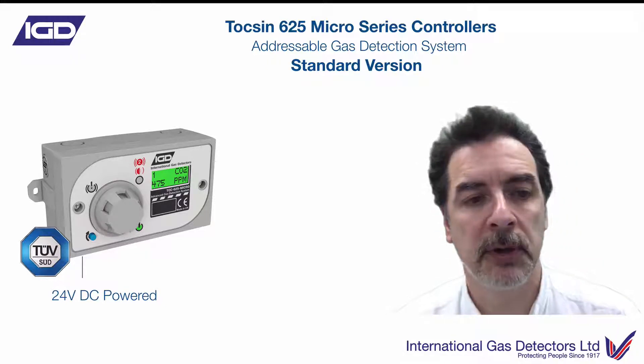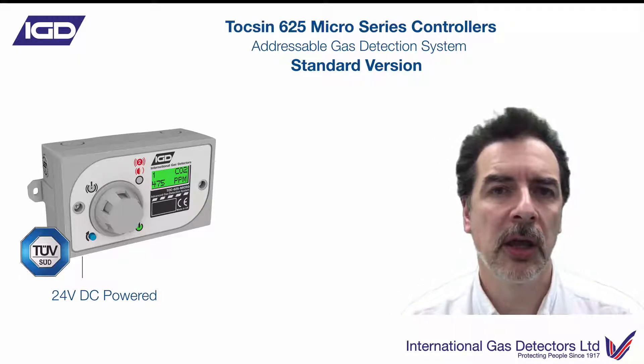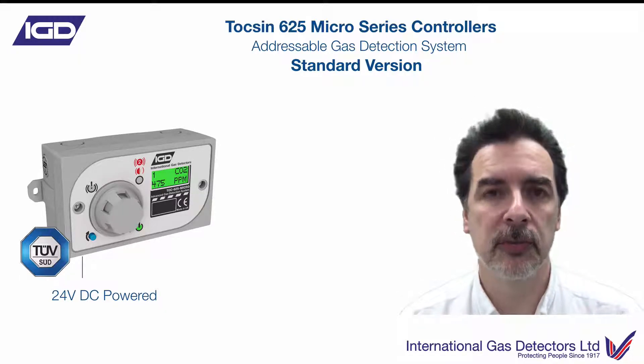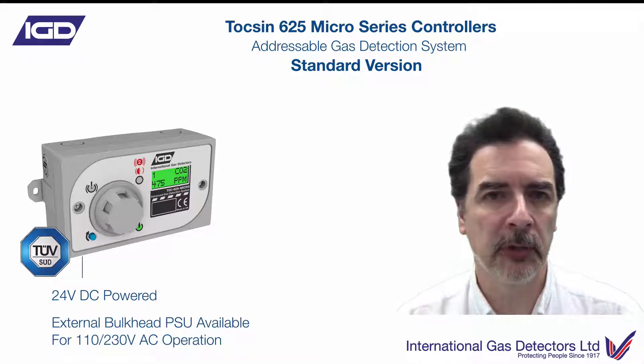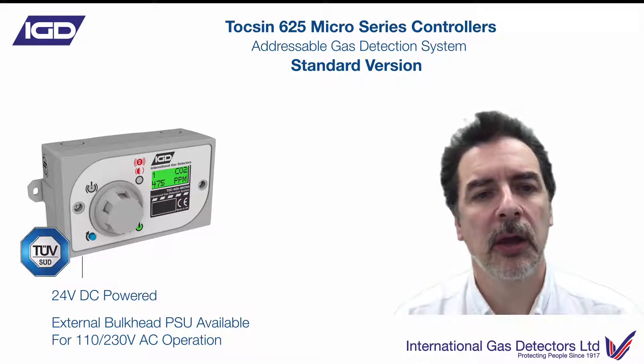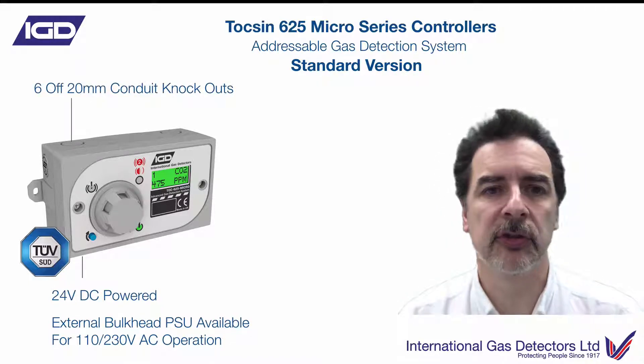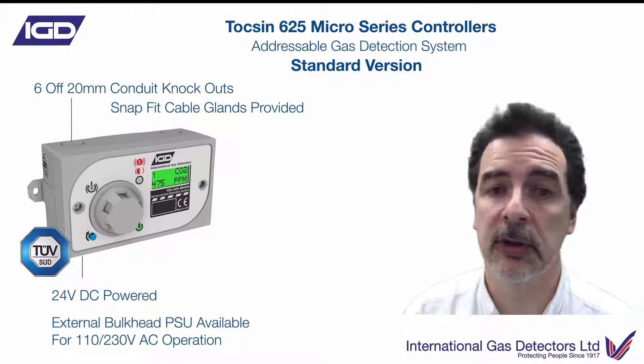You can run this from your own 24 volt supply, from a battery backup system you've already got, maybe a site UPS, or something already built into the systems you're connecting this to. Or we can supply you with a mains power supply — a bulkhead mounted power supply to go with it. It comes with standard 20 millimeter knockouts; you've got six of those on the unit and we supply cable glands to go with that.